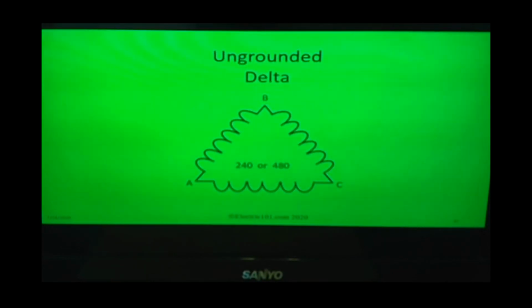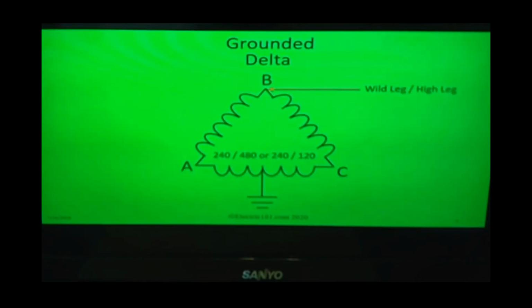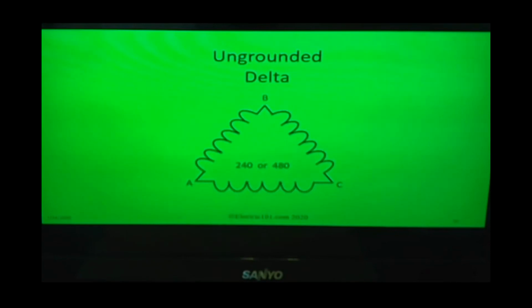Now, another circuit you can see is going to be what's called an ungrounded delta. There's a lot of circuits that are grounded, such as this one and this one, and there's a lot of circuits that are not grounded. Now, in all reality, if you have three-phase equipment and all you run is three-phase equipment, you don't need a neutral conductor. So these systems are permitted to be ungrounded, but once they are ungrounded, there's a whole host of safety factors that have to be complied with.